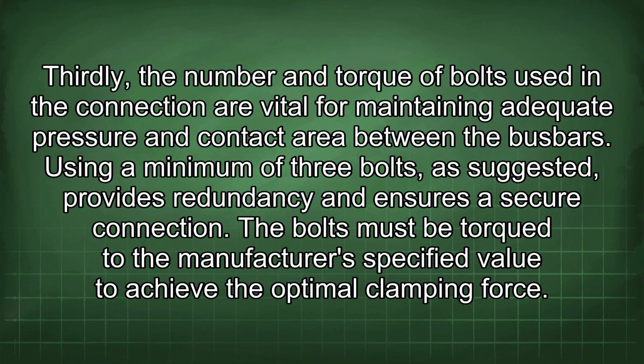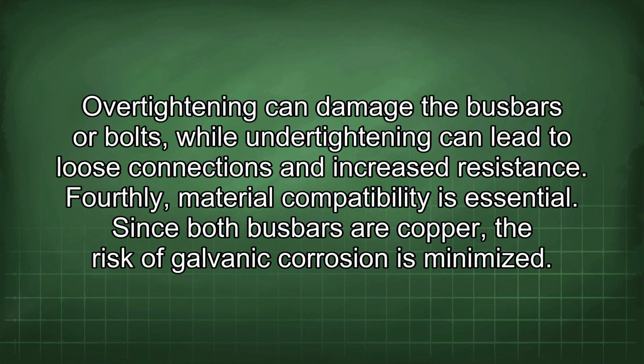Thirdly, the number and torque of bolts used in the connection are vital for maintaining adequate pressure and contact area between the bus bars. Using a minimum of 3 bolts, as suggested, provides redundancy and ensures a secure connection. The bolts must be torqued to the manufacturer's specified value to achieve the optimal clamping force. Over-tightening can damage the bus bars or bolts, while under-tightening can lead to loose connections and increased resistance.